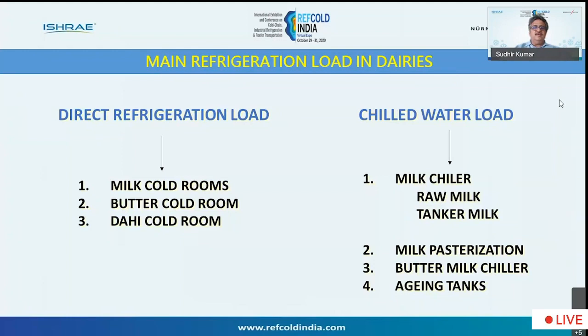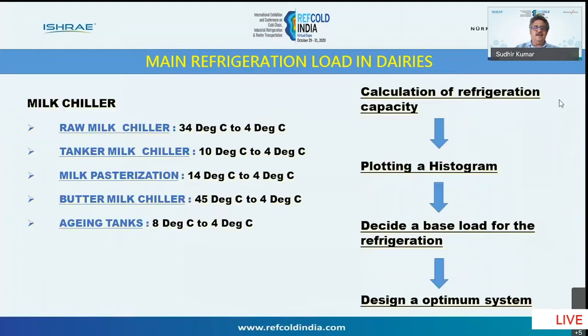So basically, direct refrigeration and indirect refrigeration. The various processes of indirect refrigeration use chilled water. We use chilled water at close to 0 degrees, either from an IBT system or from a PHE system. We give the chilled water to the various processes in the dairy. Basically, the raw milk chiller, where the milk is cooled from 34 degrees to 4 degrees. If it is a tanker milk chiller, then it is from 10 degrees to 4 degrees.